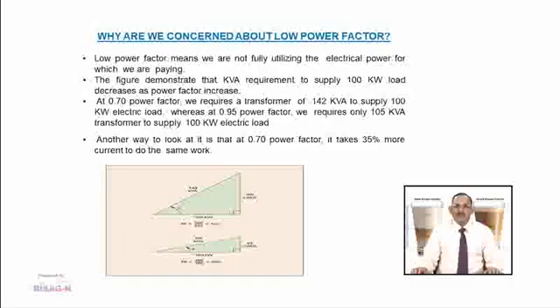Low power factor means we are not fully utilizing the electrical power for which we are paying. The figure demonstrates that the kVA requirement to supply 100 kW load decreases as power factor increases. At 0.70 power factor we require a transformer of 142 kVA to supply 100 kW of electric load, whereas at 0.95 power factor we require only a 105 kVA transformer. At 0.70 power factor it takes 35% more current to do the same work.